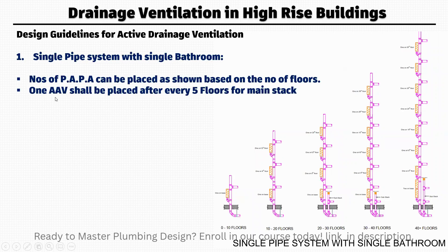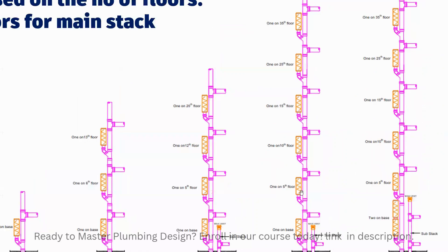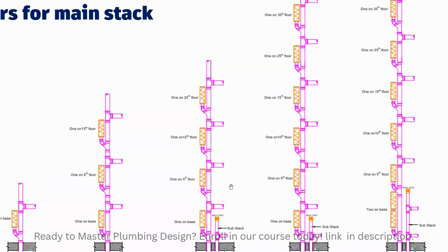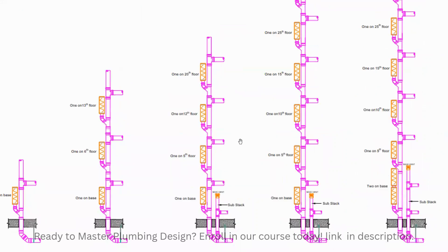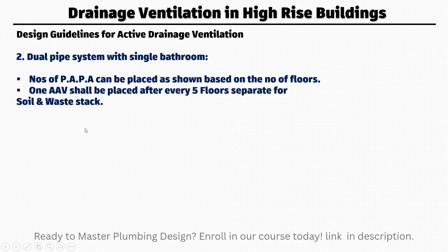One air admittance valve shall be placed after every five floors for the main stack. Similarly, for every five floors you need to place an air admittance valve on the stack, and one will be required for every branch. So this is the case for the single pipe system.